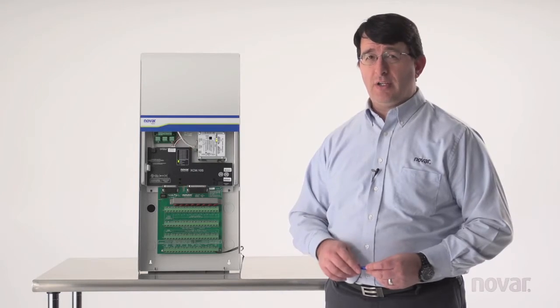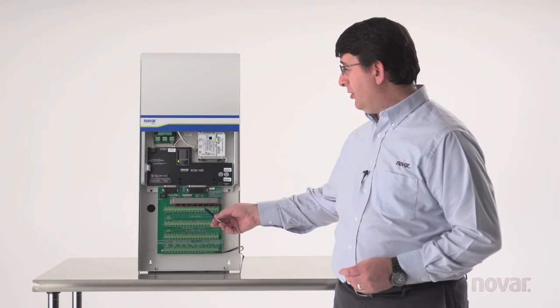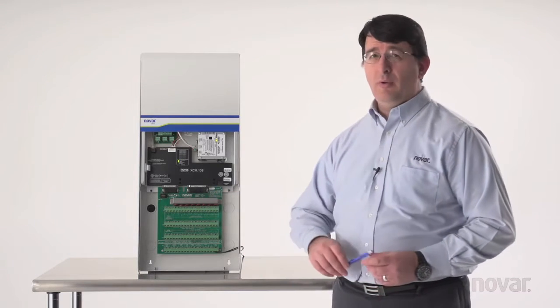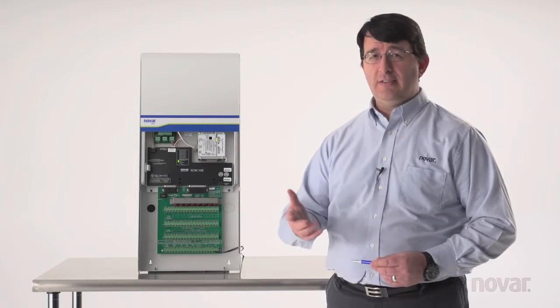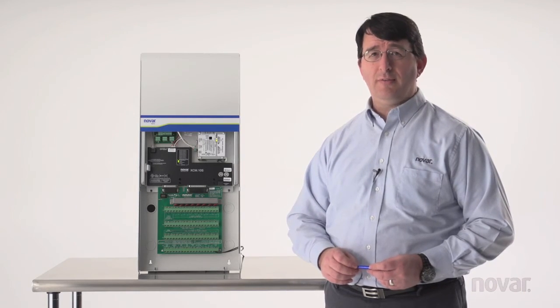One leg from this transformer should be jumpered across to each one of the outputs. That way, when the output is energized, it sends that voltage out to the device which is being controlled in the field.